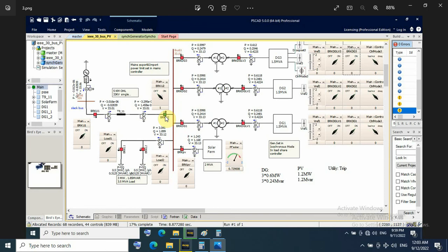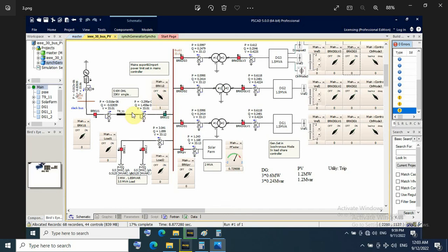And now here in this case, utility breaker trip. So in this case utility breaker trip. So also the system stable. The PV unit 1.2 megawatt, and DG 0.6 megawatt. That mean if this breaker or utility trip, that mean our system will be stable for 3 gensets.